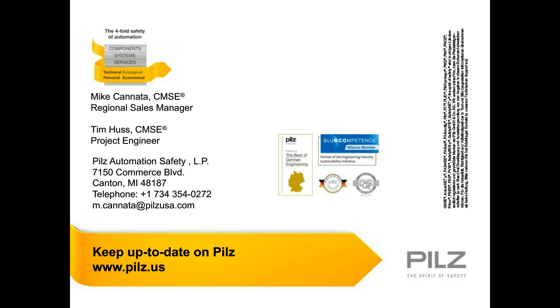What means are taken to be sure that nobody can open the SLS cabinet and have access to contactors while workers are protected by the SLS? There are Lexan panels that cover up the whole power section. It allows you to connect your incoming power lines and your load lines on the output of the system. But other than that, you would have to remove the Lexan panel, and on that panel are the tamper-proof seals.